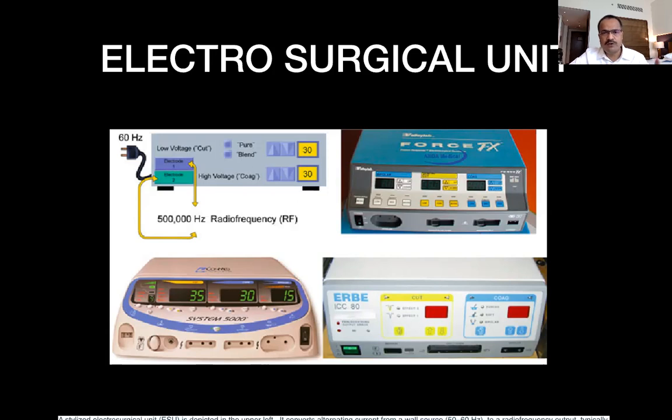Secondly, these machines allow you to change the voltages. If you open an electrosurgical unit, you will find different grids like this, which will convert this 60 Hertz into different forms of energy, different waveforms. Depending upon what waveform you are using, you will get that effect. Now, if I am a gynecologist, a certain waveform is most commonly used in my surgery. But nowadays you get such heavy and expensive machines where they will have many grids. And maybe some energy is useful for a neurosurgeon, some energy is much more dedicated for a urologist.